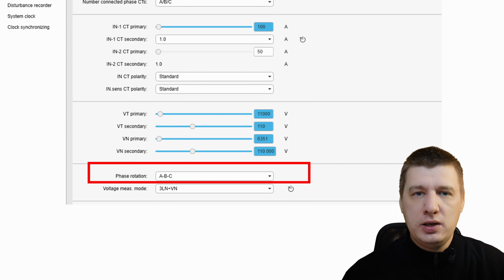When set to 1-2-3, the relay calculates line-to-line voltage, for example, by subtracting the phase 2 vector from phase 1. ACB or reverse rotation occurs when the phases reach their peak in the order of 1, then 3, then 2. This isn't necessarily a fault, but it's how some power systems are designed to rotate. If your primary system rotates this way, you must tell the relay by selecting 1-3-2 in the software. If you don't, the relay will think your system is under a constant phase reversal fault.